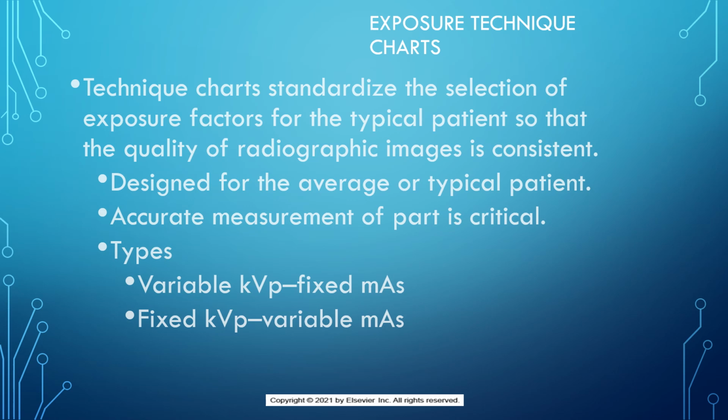All strategies, all pre-published techniques, default techniques, if you will, even in APR, before you make any adjustments, the first technique that is suggested to you on the APR software is for average habitus. If you happen to come across a paper technique chart, those techniques are for average habitus.